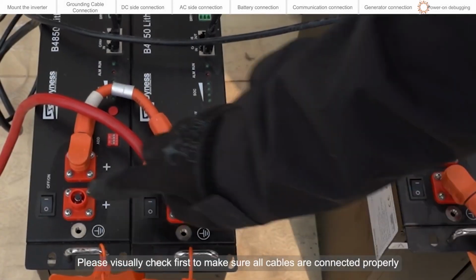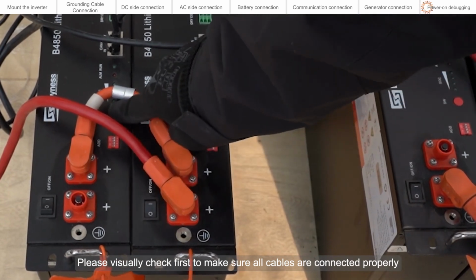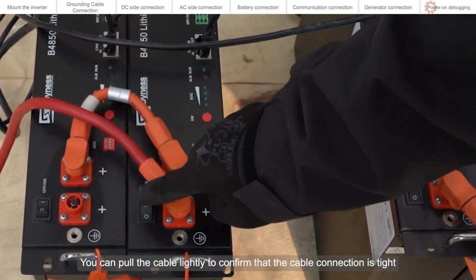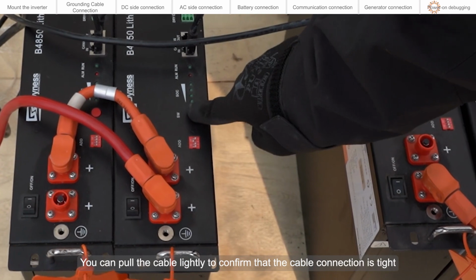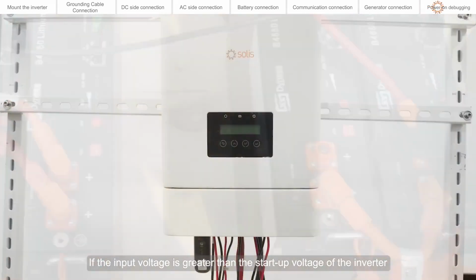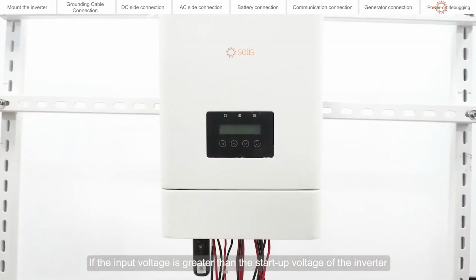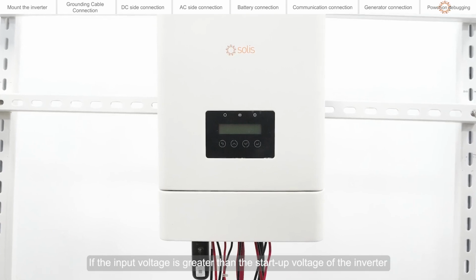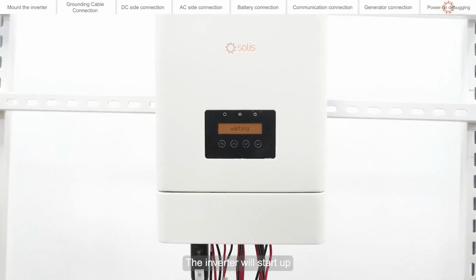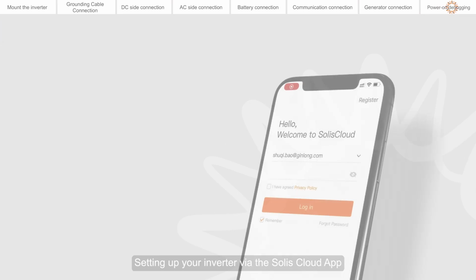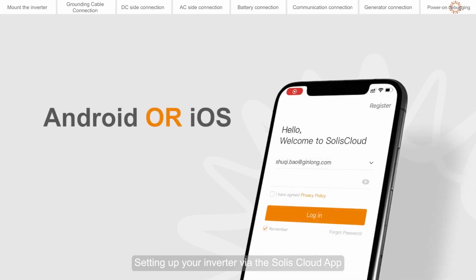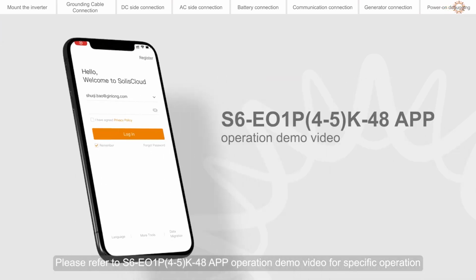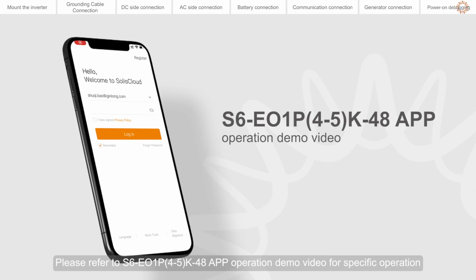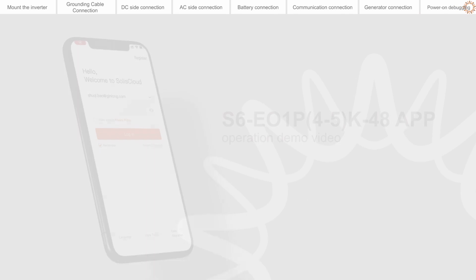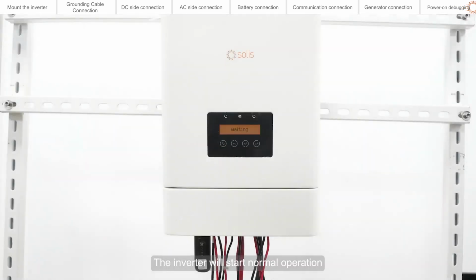Please visually check first to make sure all cables are connected properly. You can pull the cable lightly to confirm that the cable connection is tight. If the input voltage is greater than the startup voltage, the inverter will start up. Set up your inverter via the SOLIS Cloud app. Please refer to the S6-EO1P(4-5)K-48 app operation demo video for specific operation. The inverter will start normal operation.